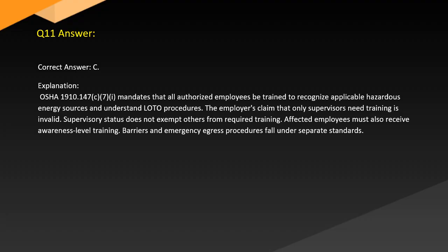Answer. Correct answer C. Explanation. OSHA 1910.147(c)(7)(i) mandates that all authorized employees be trained to recognize applicable hazardous energy sources and understand LOTO procedures. The employer's claim that only supervisors need training is invalid. Supervisory status does not exempt others from required training. Affected employees must also receive awareness level training. Barriers and emergency procedures fall under separate standards.